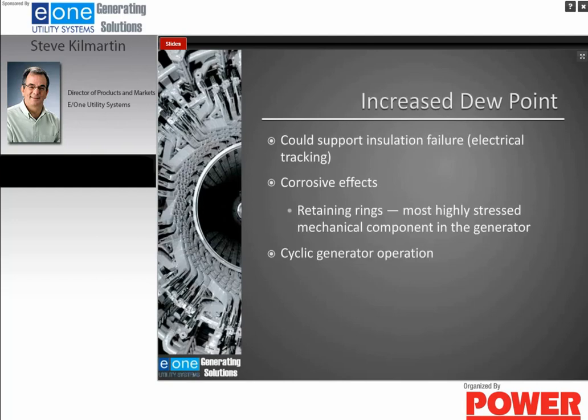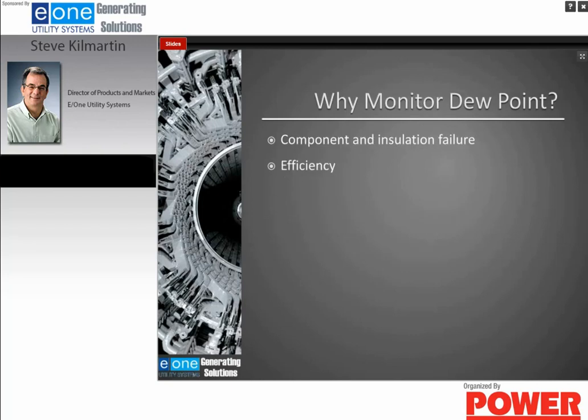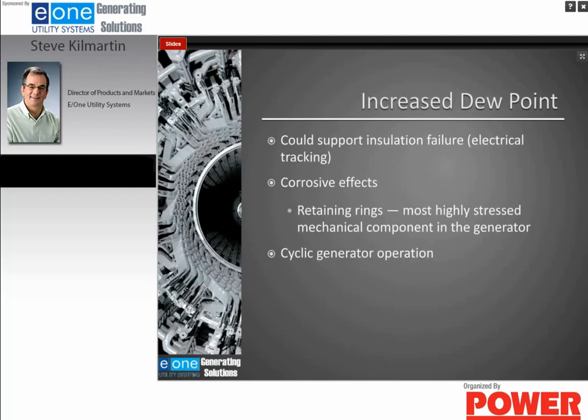Oh, by the way, back on this slide, this is all about risk mitigation. It really doesn't have anything to do with safety. However, if you lose a retaining ring, which we're going to discuss in a few minutes, it potentially could become a safety issue. Increased dew point can lead to insulation failure or electrical tracking in the machine.